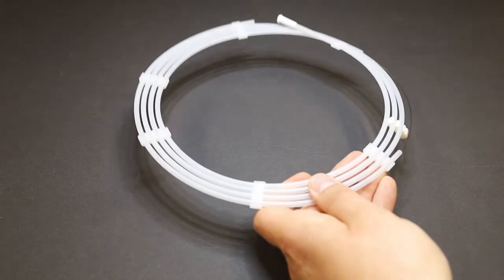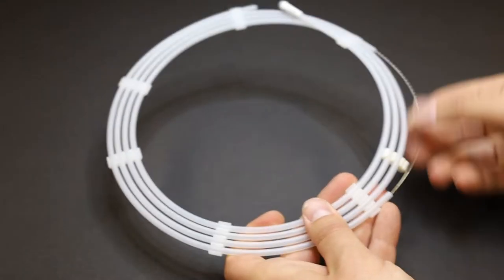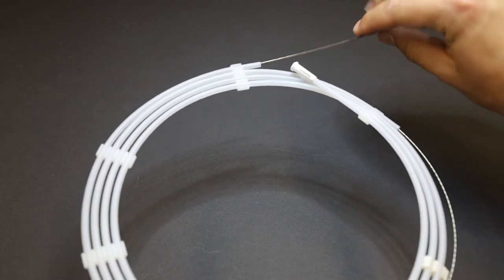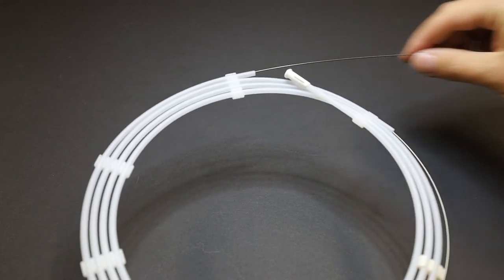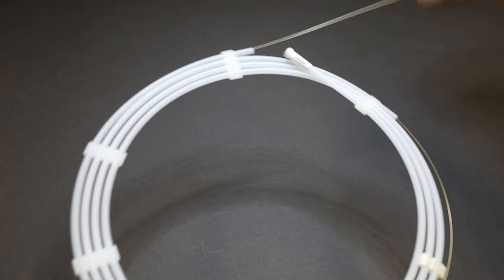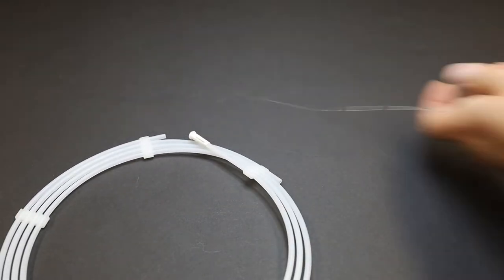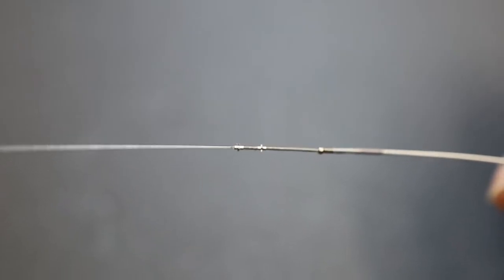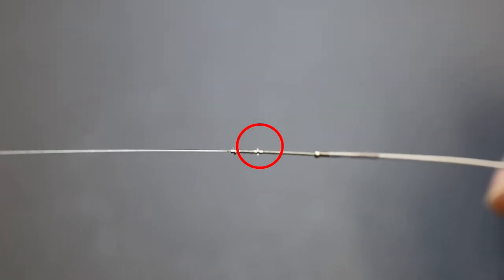We start by pulling the transport wire out of the protection tube. The wire has different sections. At the proximal end, it is stable and rigid. It can be easily pushed forward. At the distal end, it is very flexible, so you can easily navigate through the vessels. In this area, you can detect a barely visible crown. The implant hooks onto this crown so that it can be transported through the introducer and the microcatheter.